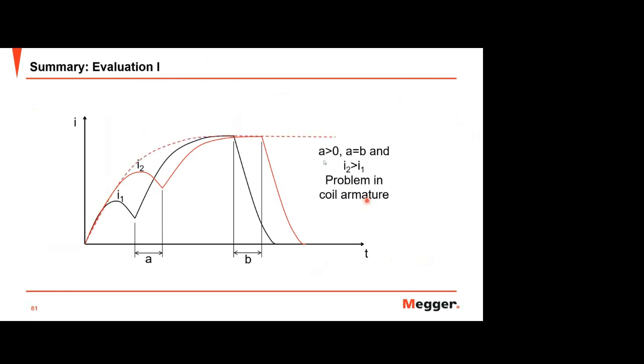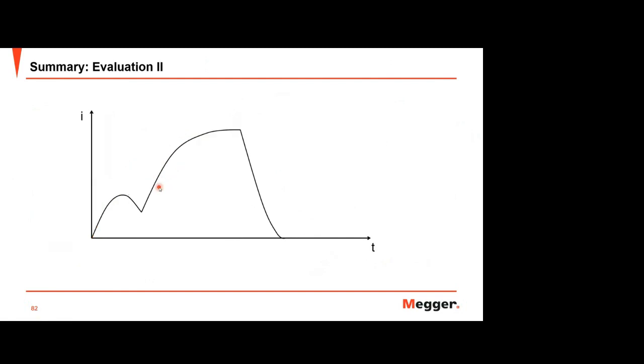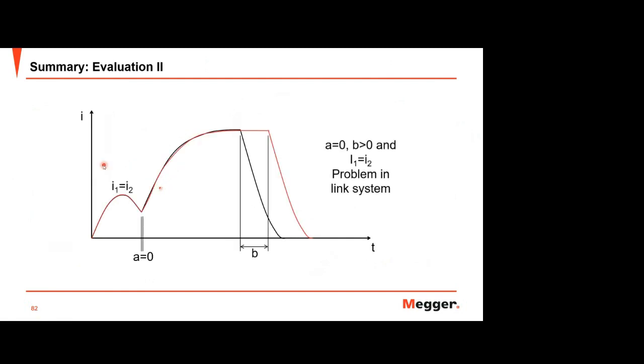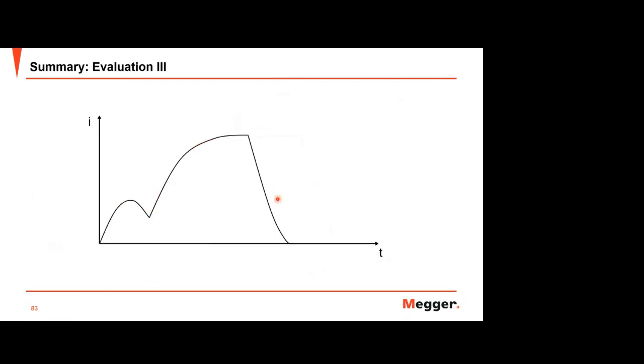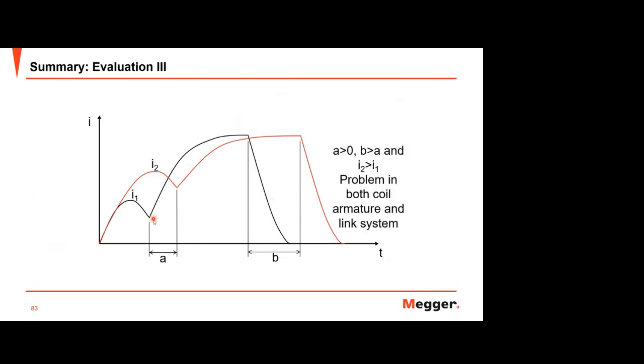So sometimes you can see like this. You cannot see the graph here at all, meaning your coil armature is totally broken. So this happens and the breaker cannot operate anymore. It cannot go to trip. If you see something, we try to avoid this. You need to investigate before this happens. Second evaluation is like this. The peak is still the same, but there is just a delay on this part. If you see this, the problem is in the link system. And third evaluation, if you see a combination of both, it means you have a problem on the armature and the link system.